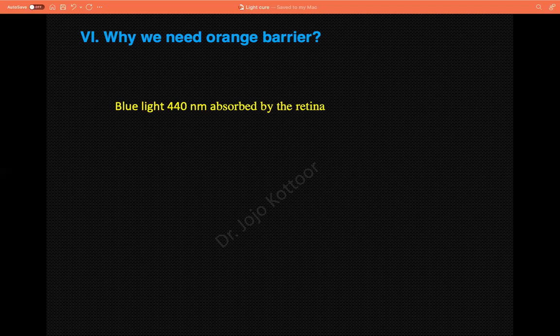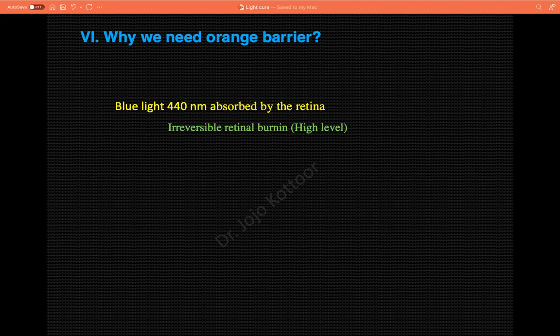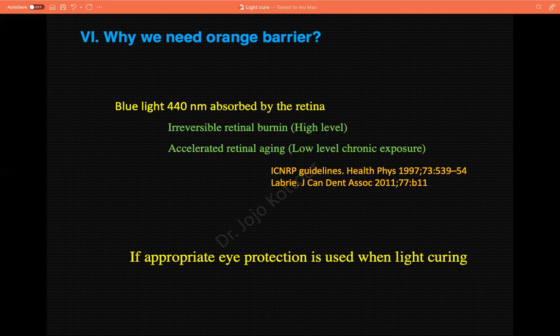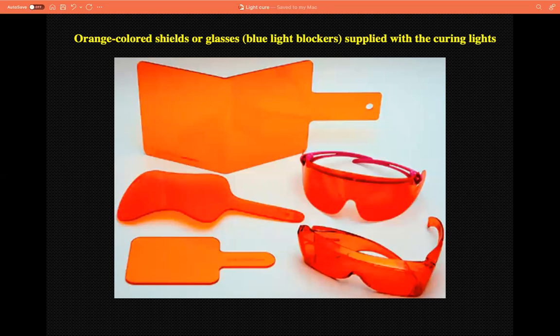The sixth: why we need an orange barrier. Blue light used for light curing — around 400nm — is absorbed by the retina. At high levels it results in irreversible retinal burning; at low levels for long duration it causes accelerated retinal aging. That is exactly why we need an eye protector when using the light cure unit. The eye protector is generally an orange shield because orange color blocks blue light, protecting our eyes from retinal damage.